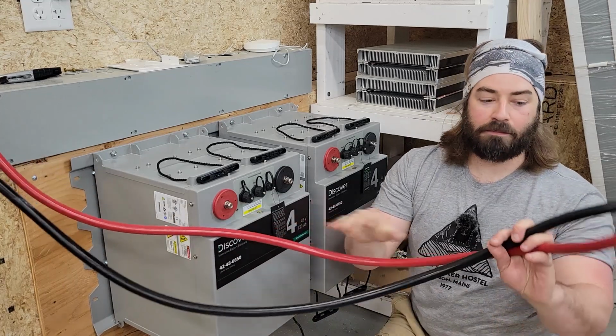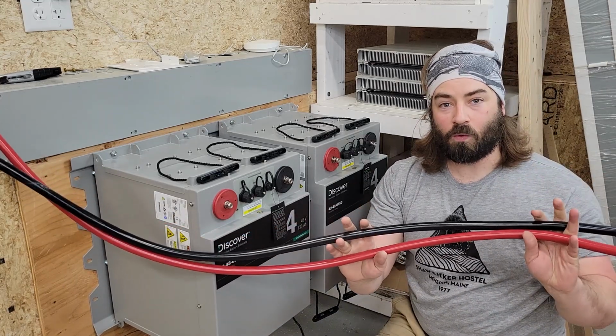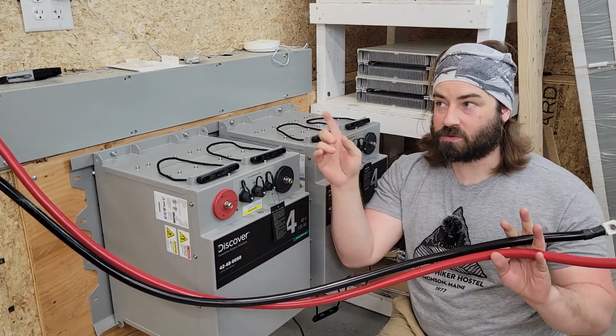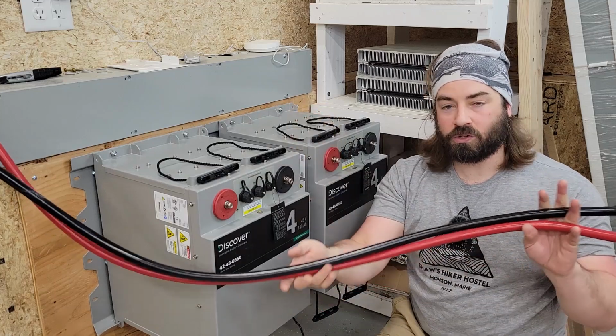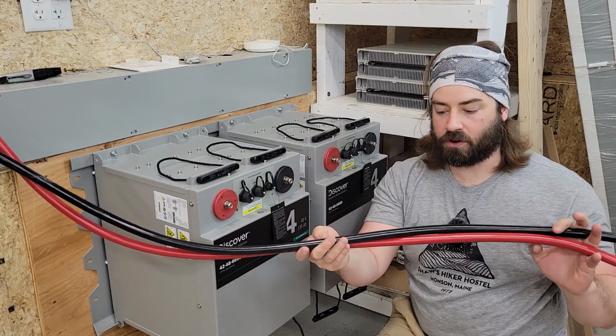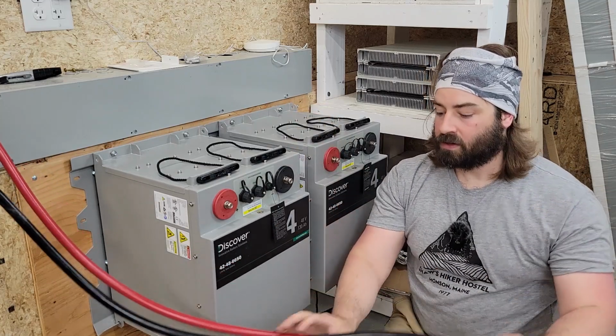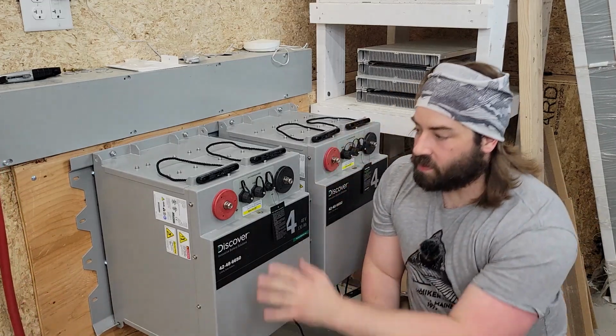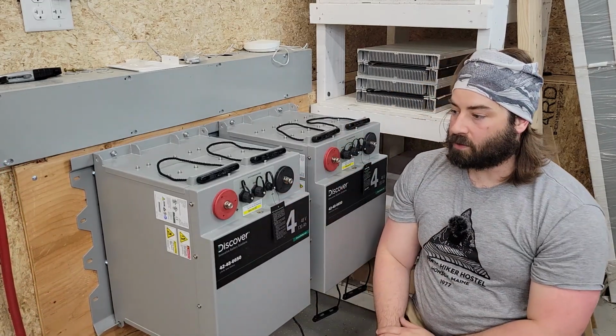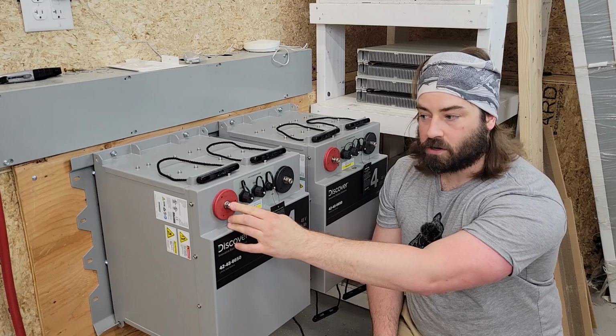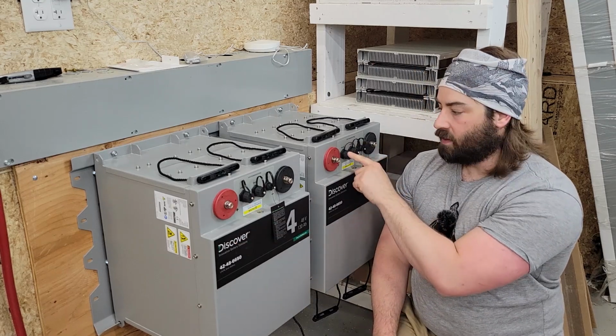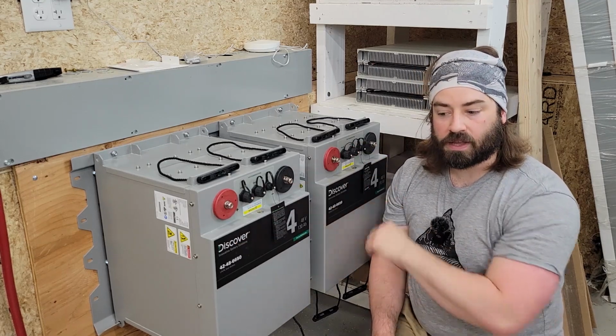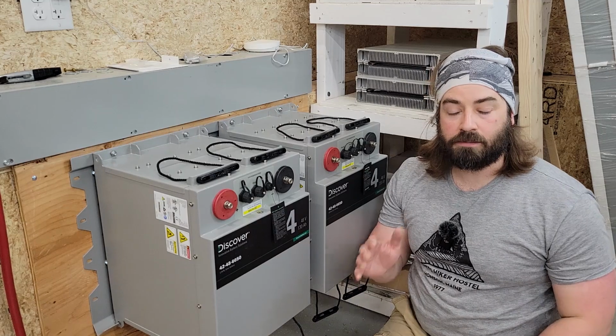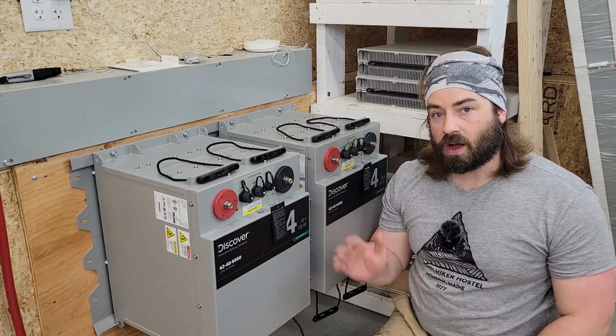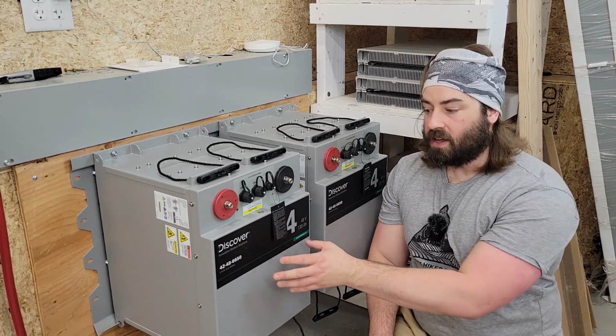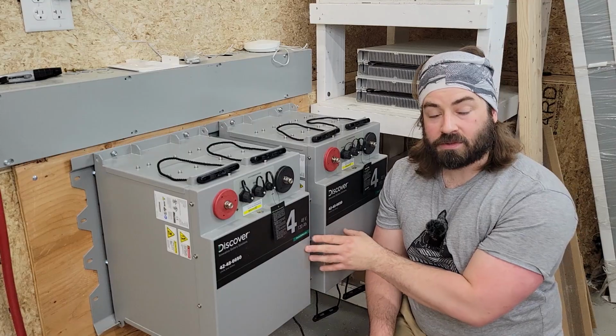I have a big pair of 4-aught wire coming down from the bus bars at the inverter, so we'll just say these wires are coming down from the inverter. Since these are 4-aught, I'll run the positive wire to this terminal, the negative over here, and then have jumpers between them. I want those jumpers to be big, so I'll use 4-aught jumpers, because remember, each one of these can do 130 amps continuous.